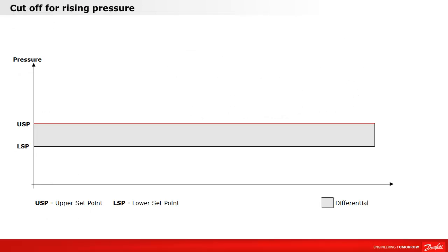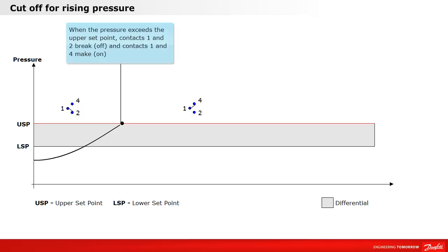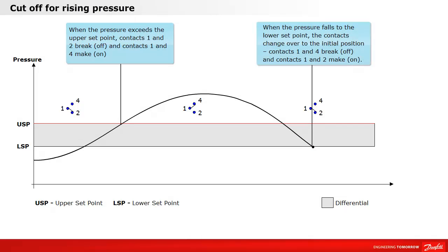Let's take a look at the cutoff for rising pressure. When the pressure exceeds the upper set point, contacts 1 and 2 break and contacts 1 and 4 make. When the pressure falls to the lower set point, the contacts change over to the initial position — contacts 1 and 4 break and contacts 1 and 2 make.